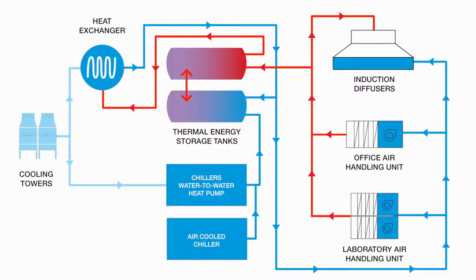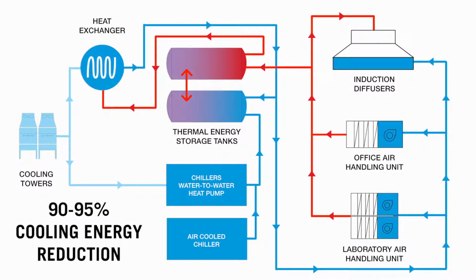And what we do in the winter months when it's cool is the cooling towers charge the thermal energy storage tanks at night when it's cooler. And in the morning we have two big tanks full of chilled water, and we can provide cooling to the building, to the induction diffusers, the office air handling unit, and the laboratory air handling units. We can do that all with cooling tower produced chilled water, and that's a 90 to 95% reduction in cooling energy.